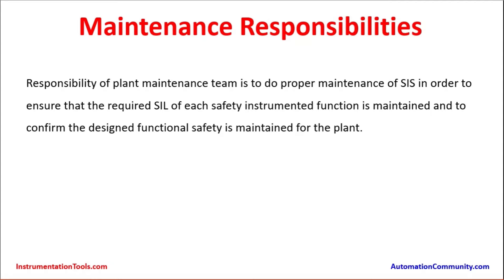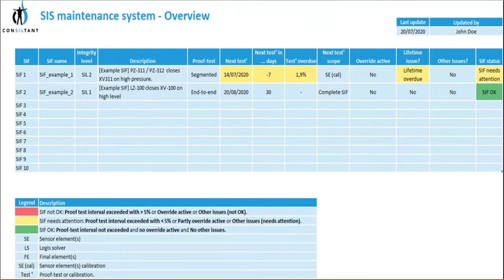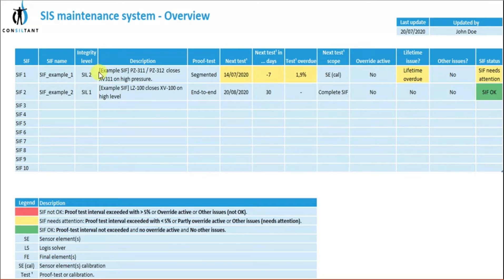Here we are seeing a sample of the maintenance system overview from an ERP tool. We can see SIF numbers SIF 1 to 10 with SIF names, Safety Integrity Levels — SIL 2 and SIL 1 types — and descriptions. For example, PZ 311/312 closes XV 311 on high pressure, where pressure instruments create the signal and close the XV, which is an on/off valve.